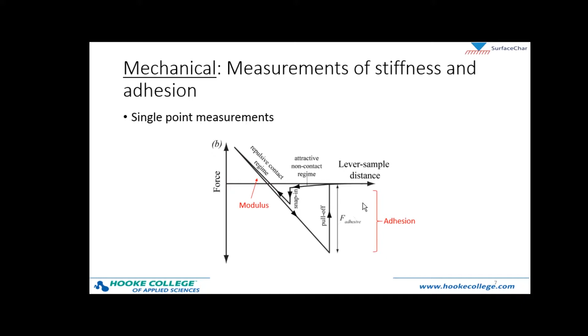And you follow the poke in as my cursor is going, and then as you retract, you can see that the approach and the retract actually do not track each other completely. And so we can get from this section of the curve information on modulus, and from this depth of what's called the pull-off when we try and retract, that gives us the adhesion information. And so we can do that at single point measurements. But we can also map that across a whole area, just create a map of these single point force curve measurements, and we can create maps of adhesion and the elastic modulus.